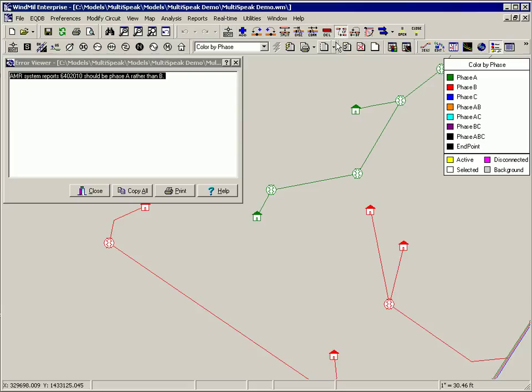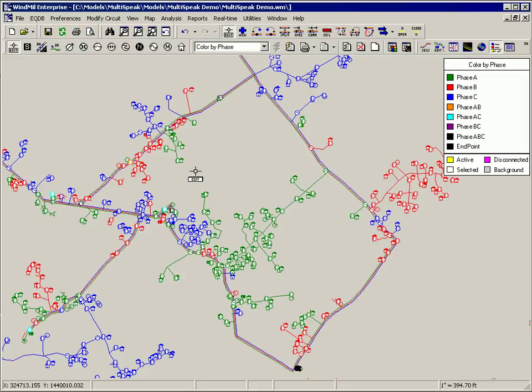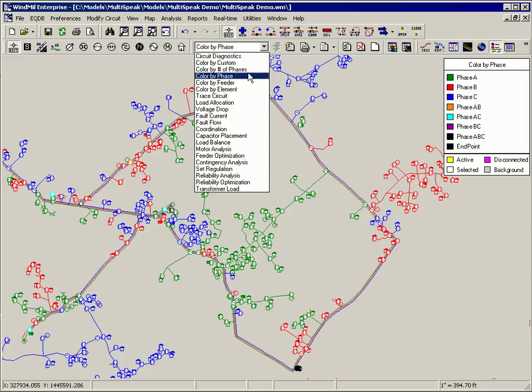The most likely explanation in this case is that whoever built the WindMil model mistakenly connected this consumer to the wrong transformer. A quick change feed operation corrects the problem. So the AMR interface has actually allowed us to identify and correct modeling problems in WindMil.